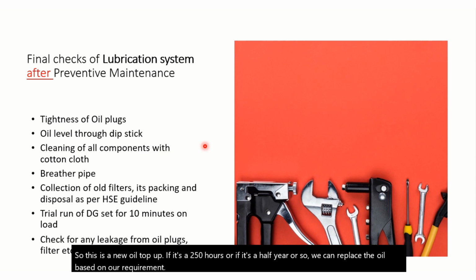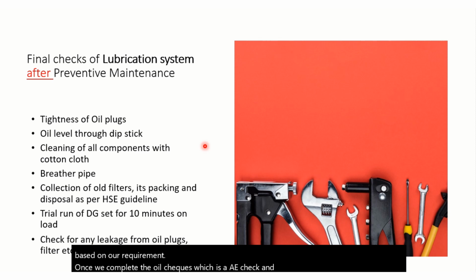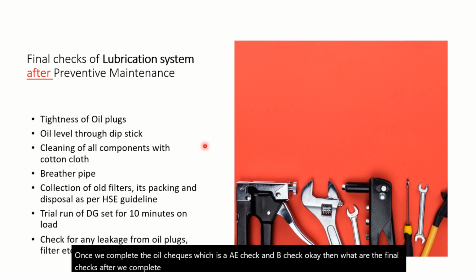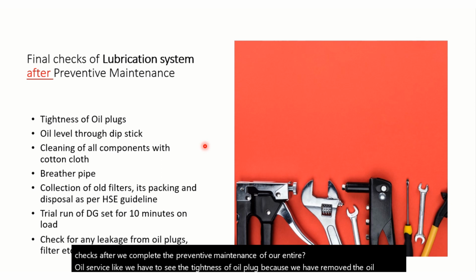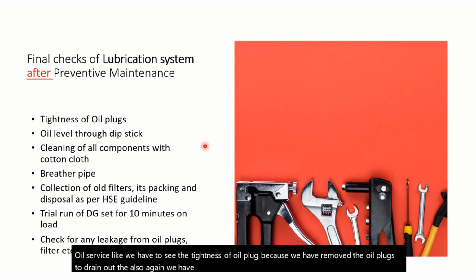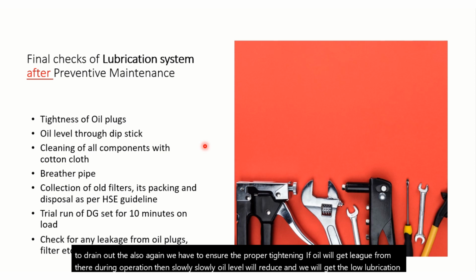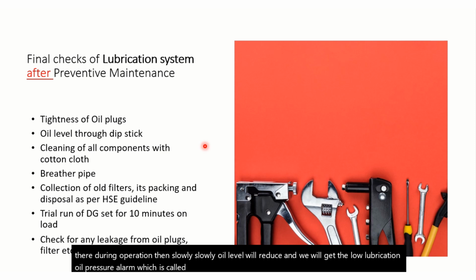Once we complete the oil checks, which are the A check and B check, what are the final checks after we complete the preventive maintenance of our entire oil service? We have to see the tightness of the oil plugs, because we removed the oil plugs to drain out the oil. So again we have to ensure proper tightening. If oil leaks from there during operation, then slowly the oil level will reduce and we will get the low lubrication oil pressure alarm, which is called LLOP, and it will create a breakdown of the engine. So we have to ensure the tightness of the oil plugs.